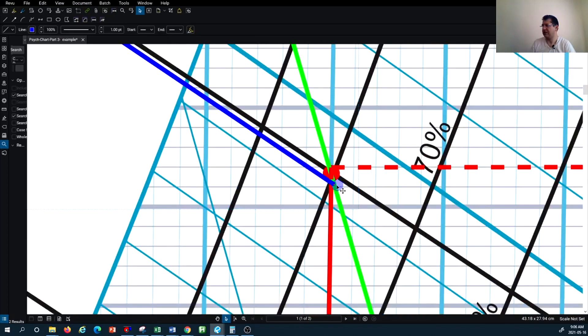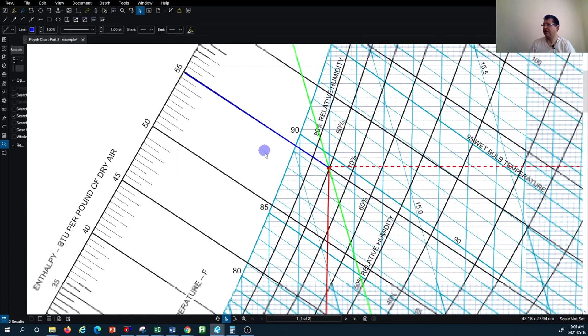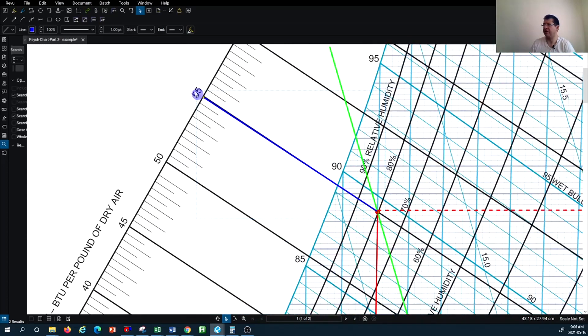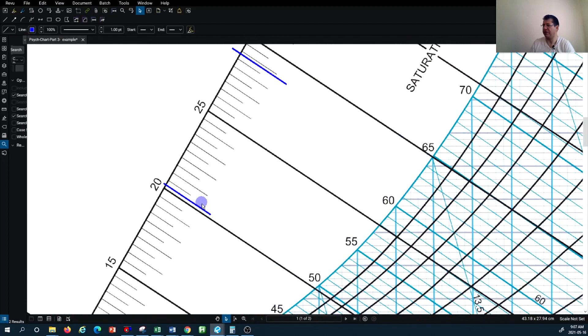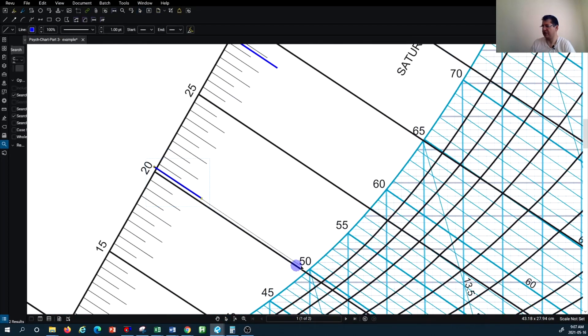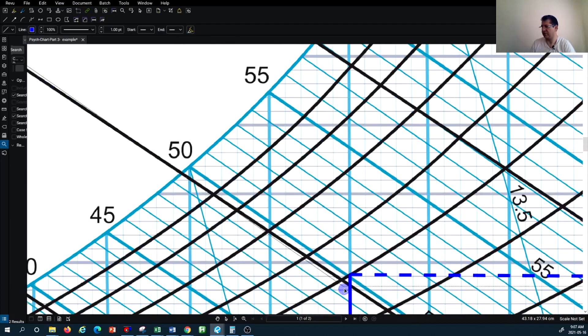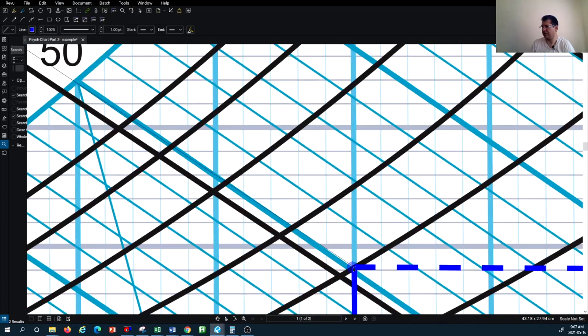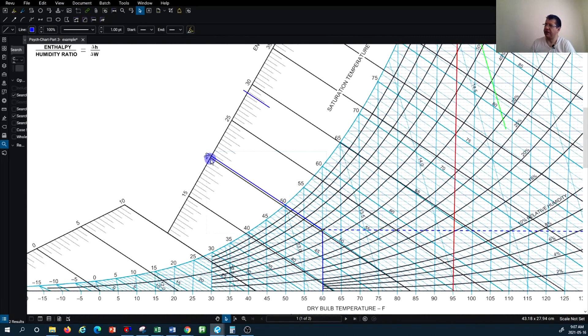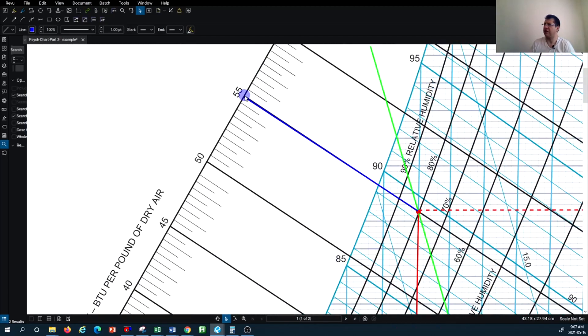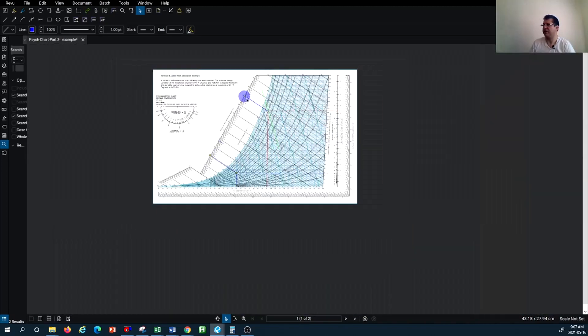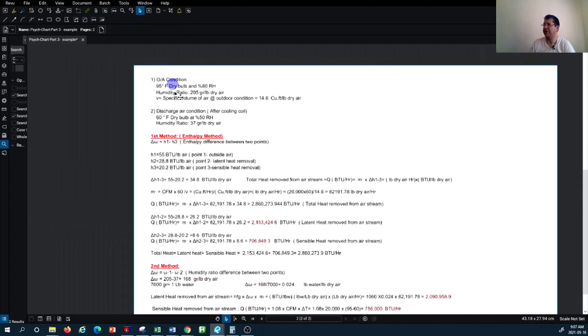You drag your line parallel to the enthalpy lines to each location. Doing that for the second point as well, the enthalpy at the second point would be approximately 20 BTU per pound of air versus almost 55 BTU per pound of air at the first point.